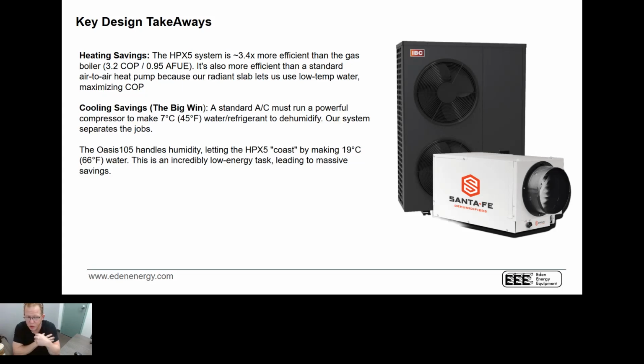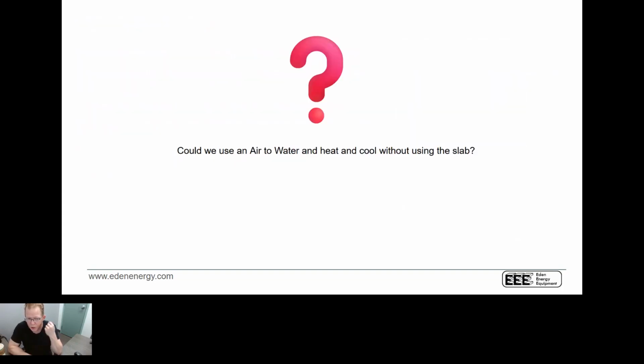Now, when you start looking at a cooling standpoint, if we're doing radiant cooling using 66-degree water because we're controlling the humidity, removing that extra latent load, well, you look at the overall efficiency of the air-to-water heat pump, it is far superior to other systems because we're not having to drive the water down to 45 degrees Fahrenheit, which makes a big, big difference. So that's a really quick overview, going very fast to make sure we don't run out of time. This is how you can do heating. This is how you can do cooling.